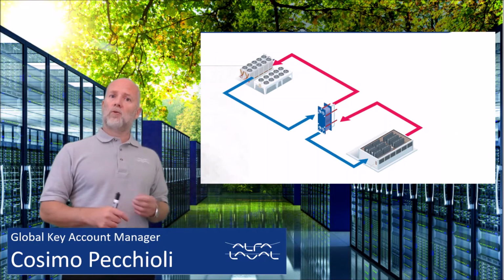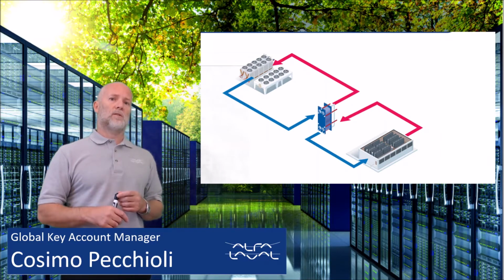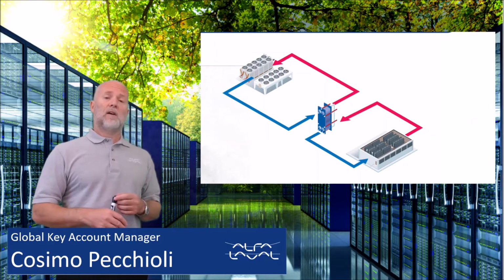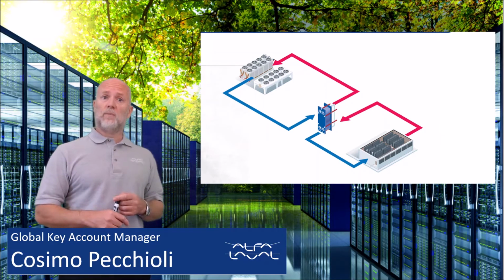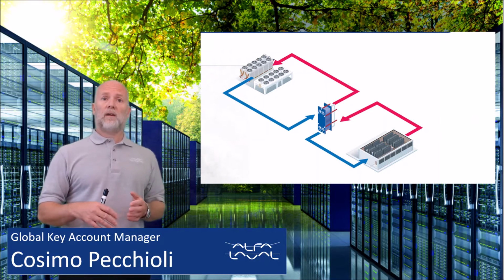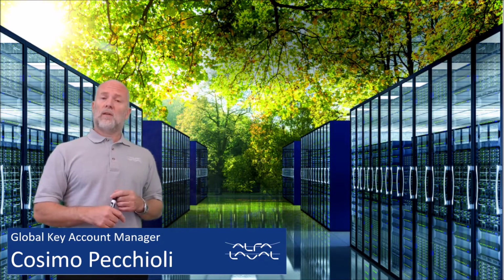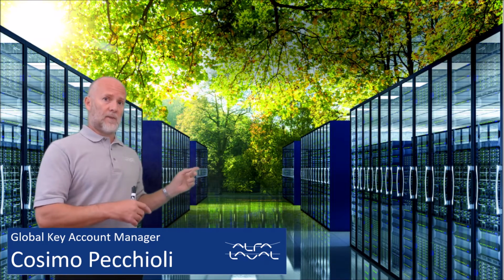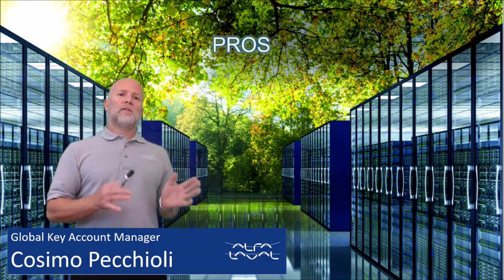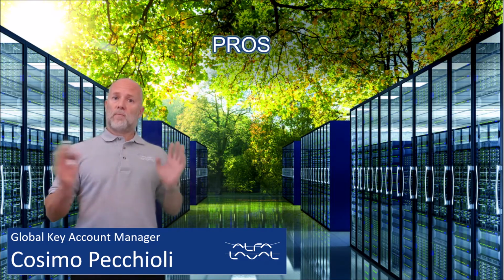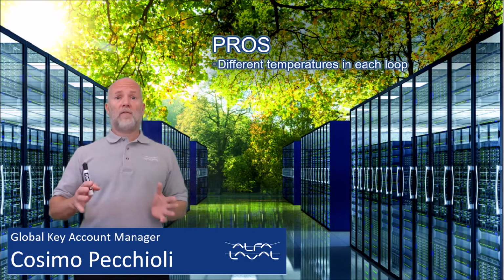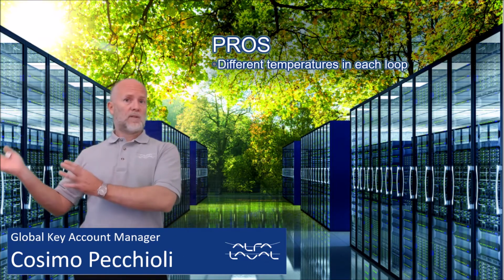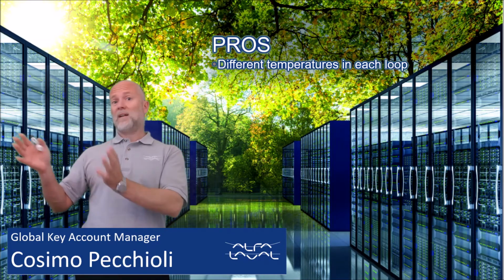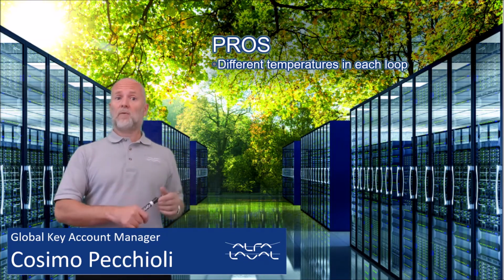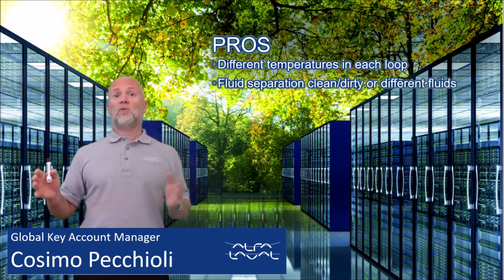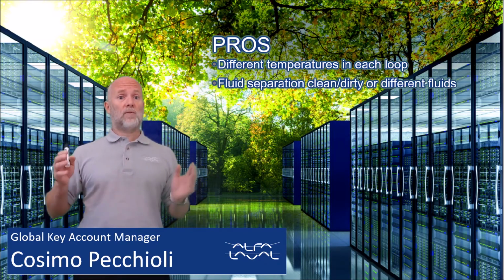What I am about to talk about now is a list of pros and cons that have been discussed at length through our meetings with the OCP, the Open Compute Project. So let's have a look at this list of advantages and disadvantages. The advantages are that you can have different temperatures between the two loops, and that you can have one dirty side, as we said. If it's an open cooling tower, that side is inherently dirtier than the other one. You can have different pressures and you can have a differential pressure between the two sides.